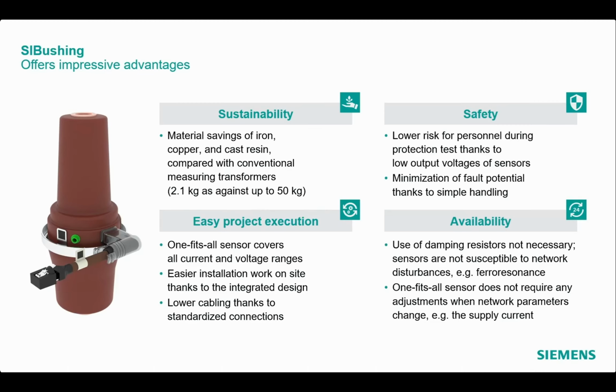We have only one SIBushing for all voltage and current ratings in the factory stock, and also a later upgrade of grid parameters is possible without adjusting any component. Also, safety on site during commissioning and testing is higher due to low voltage outputs and no need of cabling or installing of instrument transformers around or on the cables.